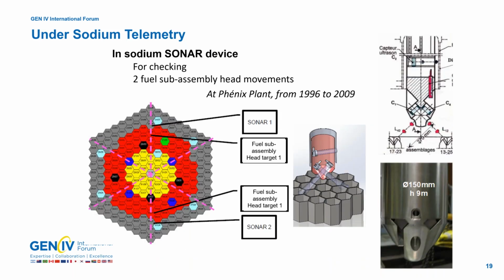Another application is a sonar device. You remember the sonar device for detecting the Titanic boat in the ocean? And here we had developed the same kind of measurement just for checking the movements of 2 fuel subassembly heads in the Phoenix plant. And that device was developed, designed, manufactured, tested, and used during more than 10 years in Phoenix plant. And it was located just above the core outlet and operating at more than 500 degrees C.